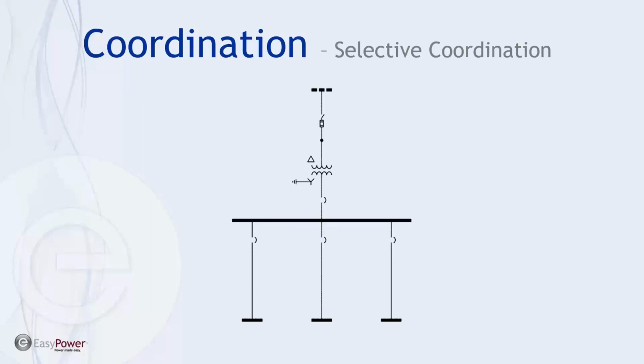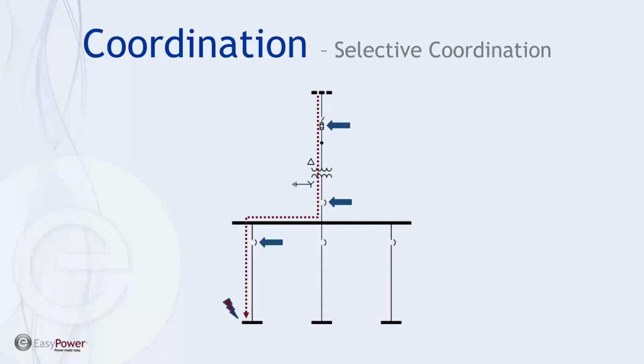So a case in point would be a typical radial distribution system like this, where we have a potential for a fault in one of the downstream buses or downstream loads. And if we, let's say, experienced a fault in this particular bus or equipment, then that fault current would be sensed or felt by at least 3 protective devices: the feeder breaker in the fault line itself, the main breaker of the switchboard or the distribution panel, and then the primary protection for the whole plant or the substation. Now, because this fault is going to be substantial compared to the normal load current, any of these 3 devices would be potentially tripping.